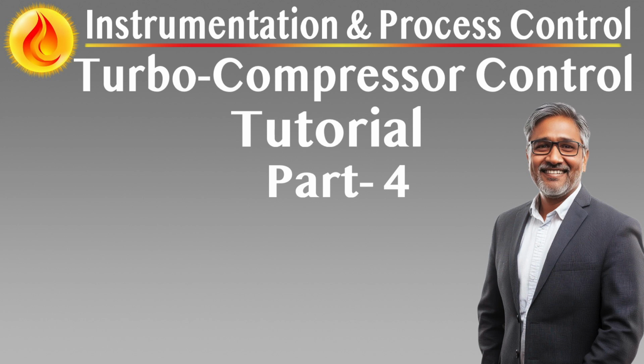Sequence of events, SOE recording. Critical for diagnostics and root cause analysis, alarm and event discrimination with a resolution of 100 milliseconds, even during bursts of up to 100 events per second. Full synchronization with DCS clock for unified plant event logs. Vibration monitoring system. Real-time data from vibration probes and proximity sensors must be updated at the TCCS within 2.5 seconds maximum. Support simultaneous viewing, alarming, and logging across all active channels.